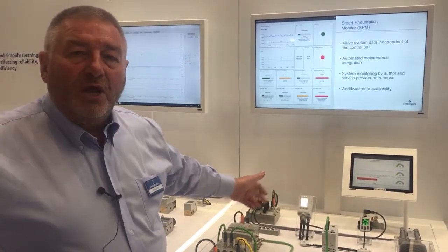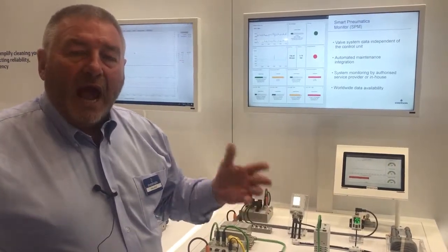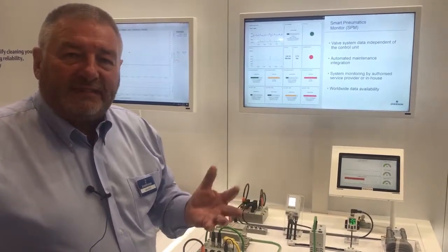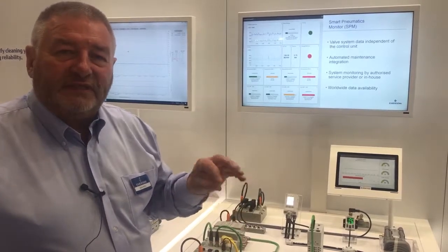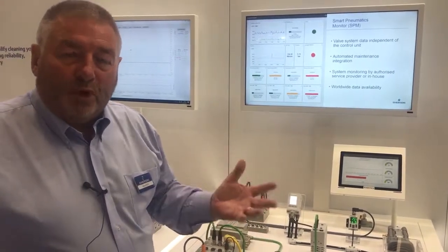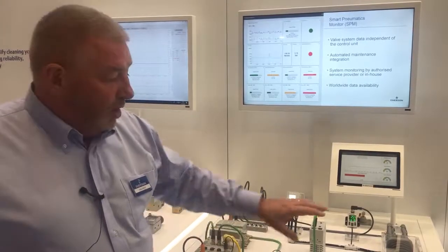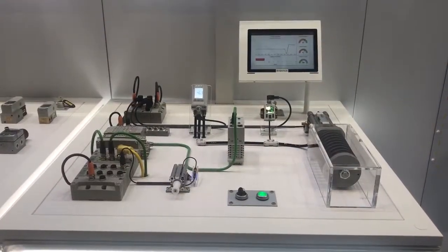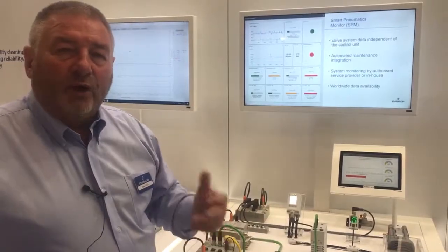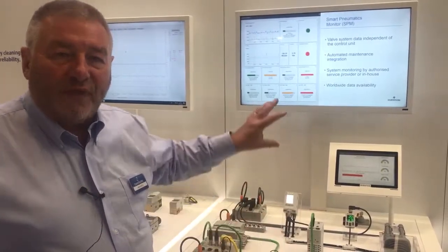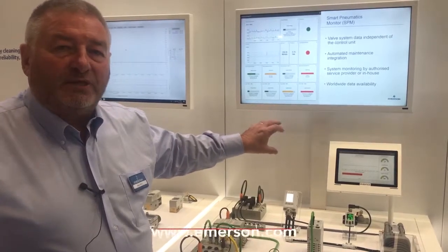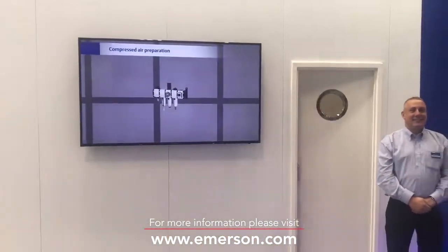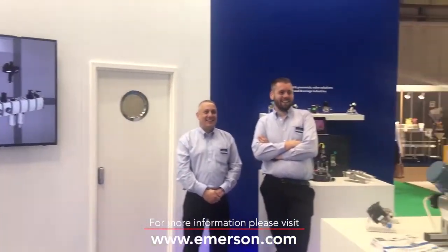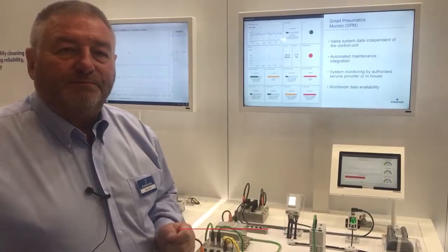This will give us instantly the life expectancy of the valves. Every time this is operated, it will remove one cycle, and that will tell the operator when the predicted lifetime will end, so they can put this into planned maintenance, so we don't have unscheduled downtime from the machines. Also, with the cylinder travel, we can measure the distance of piston seal travel, and also the velocity of cylinders along with the air consumption in any particular part of the plant. So this is giving real-life analytics to your process to allow you to prevent unscheduled downtimes.